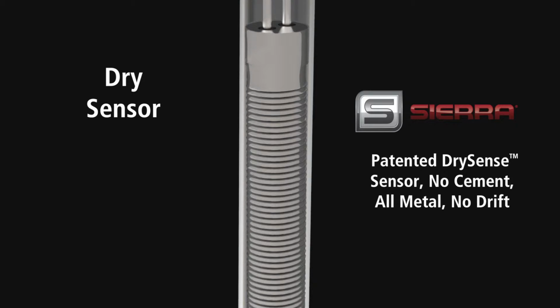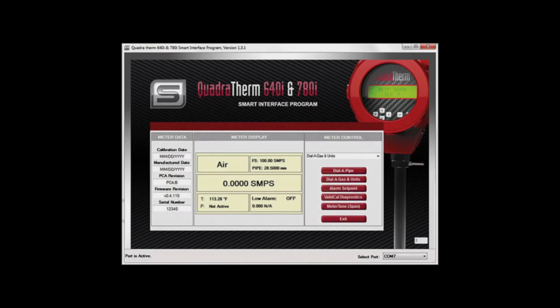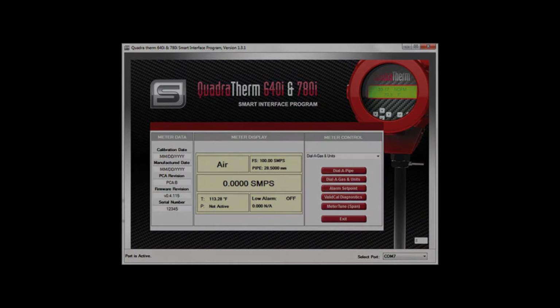Sierra's DrySense all-metal no-drift sensor has a big advantage during in-situ calibration validation. With Sierra's all-metal DrySense velocity sensor, you have the mechanical design confidence that there will be no drift and that in-situ calibration validation is indeed actually valid. Sierra offers a free in-situ calibration validation software package we call ValidCal Diagnostics.